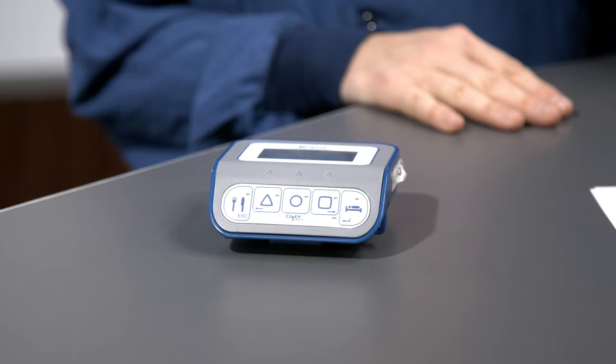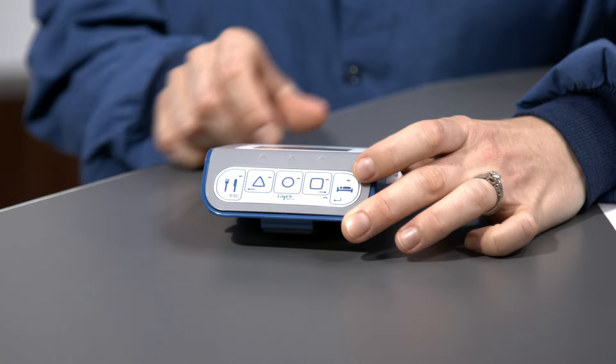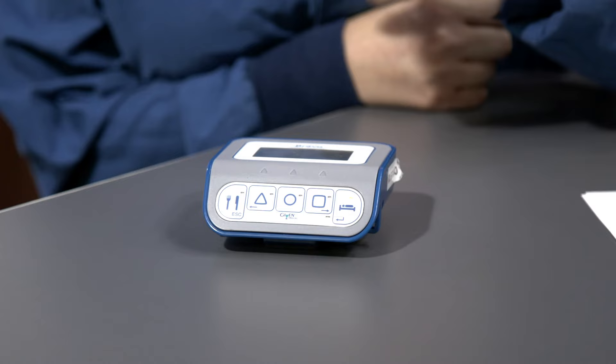Can I take it in the shower? You cannot — leave the receiver outside the shower and keep it dry, perhaps in a bag or under a towel. Whenever the receiver is too far away from you it will stop collecting data, but when you bring it back close it will re-pair. It will beep and blink red when it's too far away. There's a small light not connected to any button that blinks blue about once every 30 seconds during normal operation, and turns red when the signal is lost. When you bring it back, it will start blinking blue again.